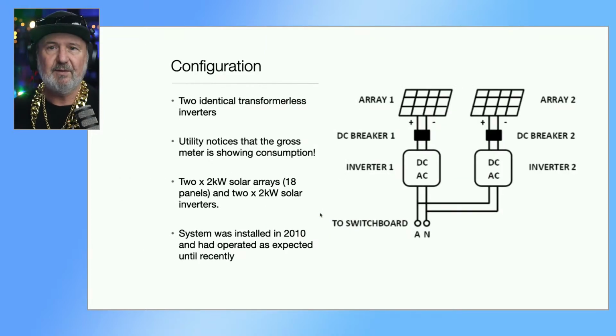Now this is the configuration of this particular system: 2 inverters, 2 PV arrays, and they're only 2 kilowatts. So a relatively small system, and he noticed that the gross meter was showing consumption. Now gross meters should only measure export from the inverter, nothing else. So that means power was coming in on the gross meter and going to the inverters.